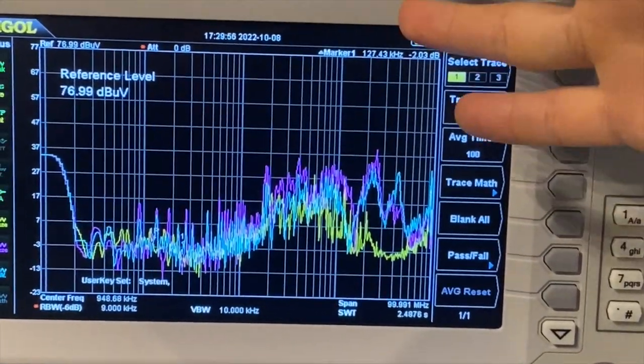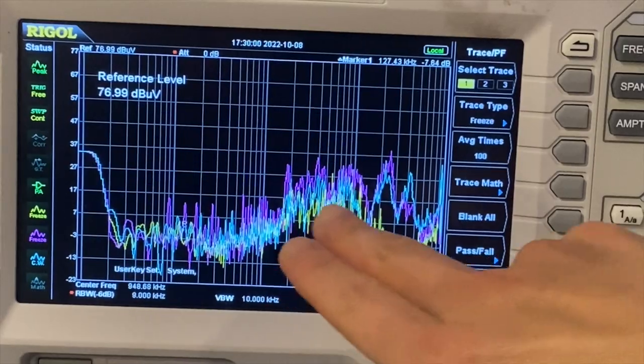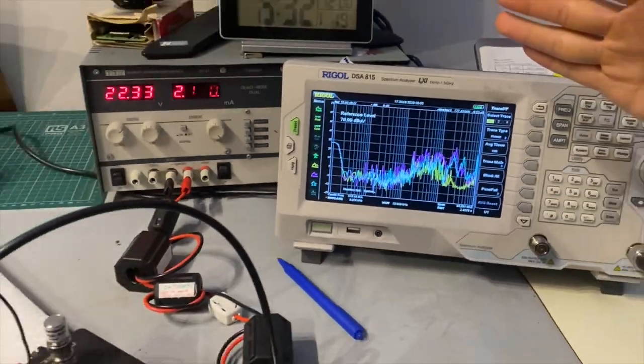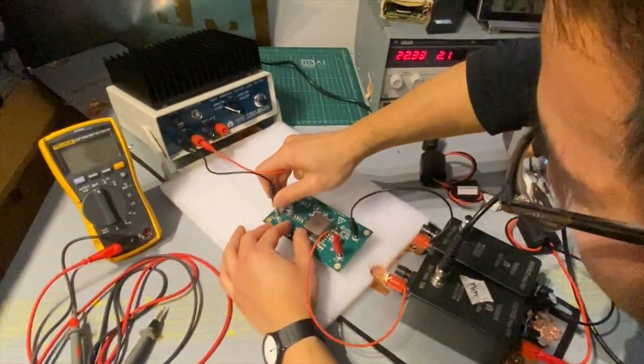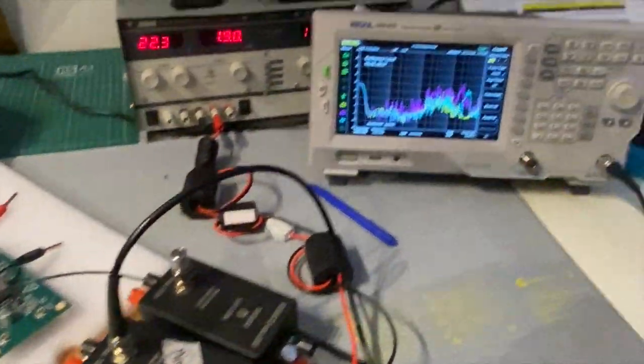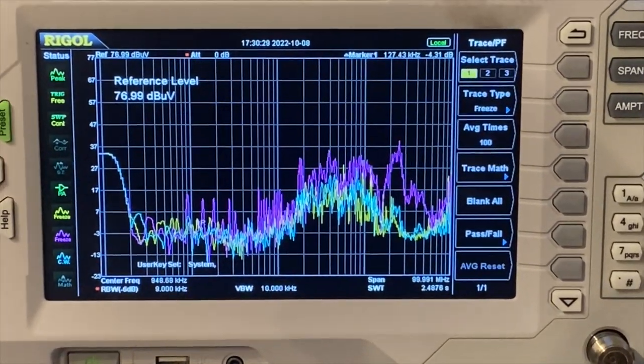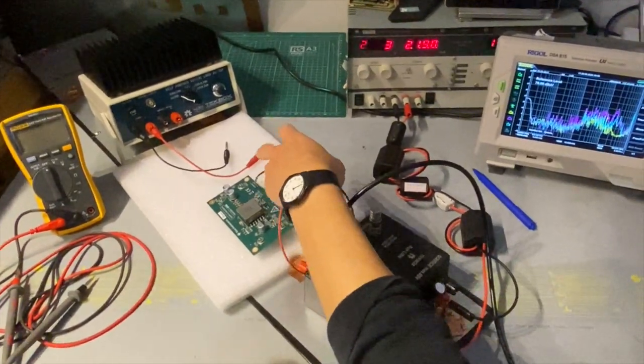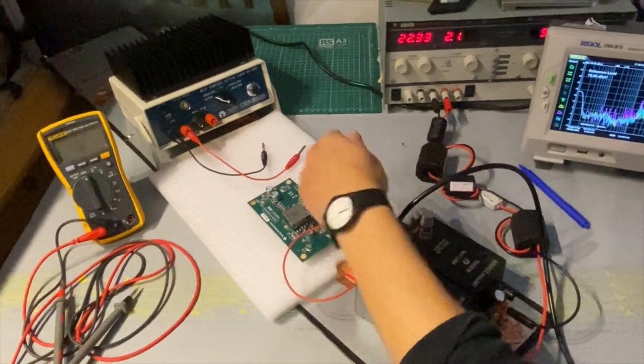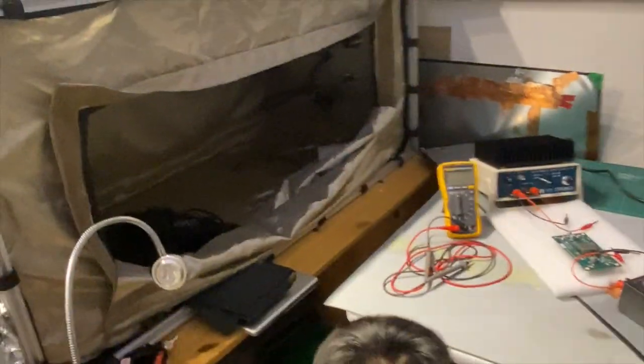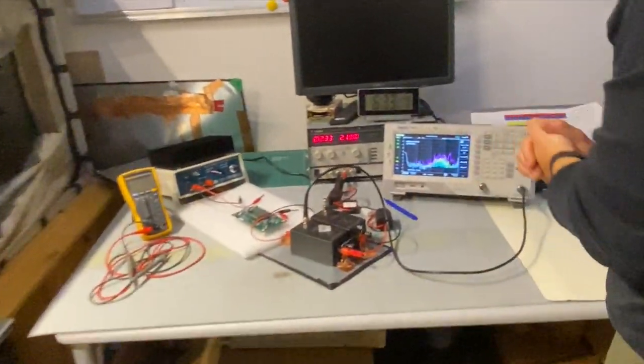So now it is back. Now at least it doesn't give you the over the limit error. And as you can see here, the blue trace actually is a lot less. Well, I wouldn't say a lot less, but it's less than the pink trace. So as we said, that long cable must have coupled noise. So what about we disconnect this cable then? Can that couple noise? Yes, as you can see, now the noise dropped even further. How about this wire? If I disconnect here, now it's even less. So clearly, as you can see, because we have a very strong emitter nearby, all these cables could potentially pick up ambient noise and causing problems. So really, if you don't have a tent as we have it here, then you probably will need to find out which is your strongest emitter and then simply kill the emitter. Once we kill the emitter, the ambient noise is much less.